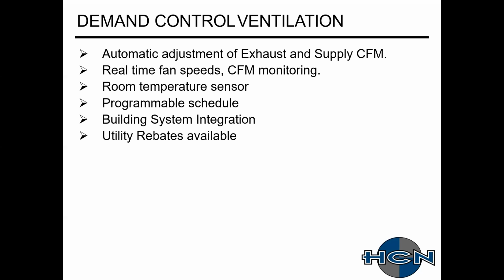So like if you're using a demand, because that actually plays into this. If you're using a demand control system, you're actually lowering, depending on what you're doing, let's say it's a low peak or low time, what's going on. You're not doing a lot of cooking. That CFM on that exhaust fan is going down. So also your makeup air is going down. But that rooftop unit in that space, let's say it's kicking on and it's sucking. So you could have a return that's actually sucking a little bit harder than your hood at that time. So you could be pulling extra heat load from that hood, just depending on where those returns are spaced out.